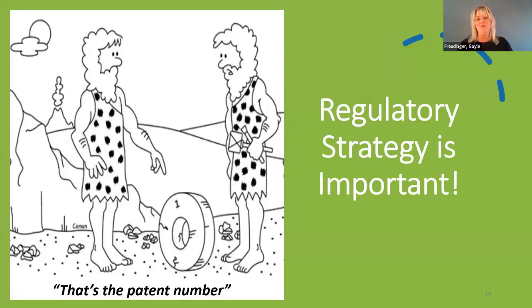Regulatory strategy up front is very important. You want to develop a regulatory strategy to make sure that your development efforts are on the right track, will be approved by the FDA, and that you're doing all the pieces necessary and required by the FDA. A regulatory strategy means you're constructing a documented plan that describes the specific steps and actions required to successfully stay compliant. It also contains the elements needed for a regulatory submission.